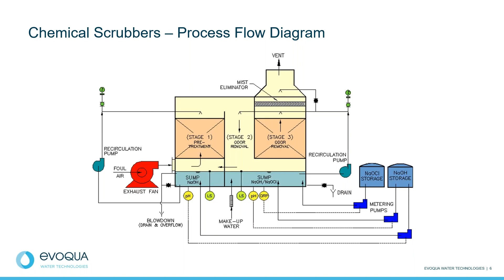As I mentioned on the previous slide, there are a lot of additional control components here. Each stage has a recirculation pump to recycle processed chemicals. We also have pH probes and ORP probes to tell the caustic and bleach pumps when they need to turn on or turn off. So now let's take a closer look at exactly what's happening in these different stages of the chemical scrubbing system.